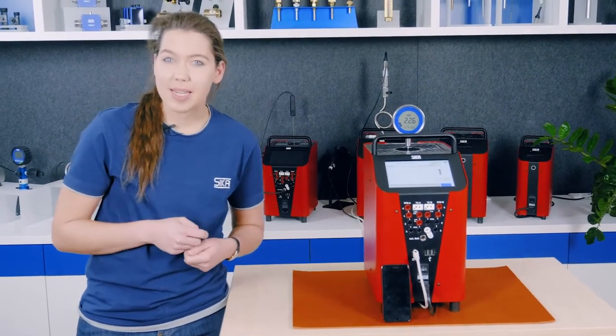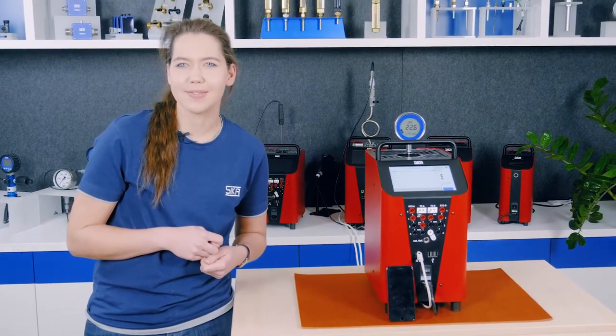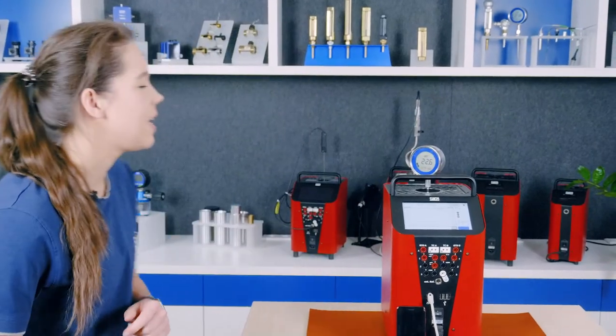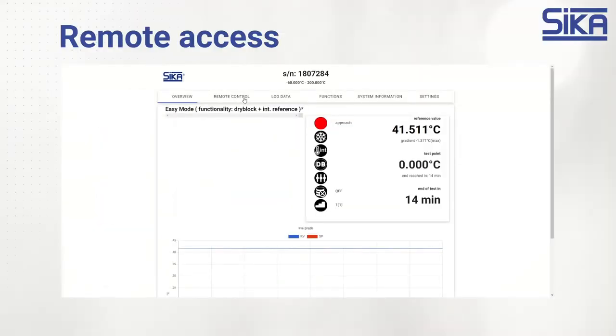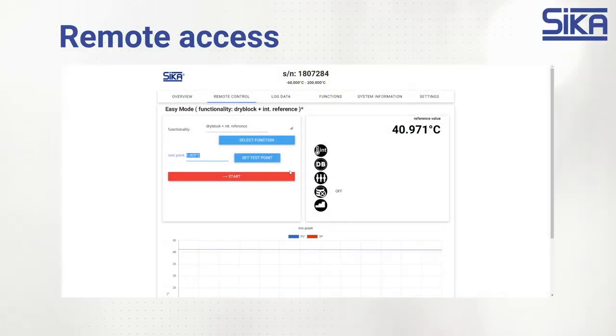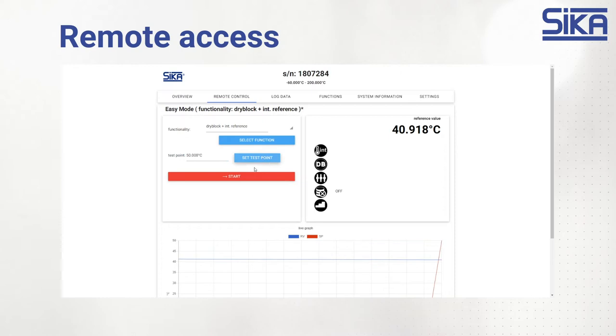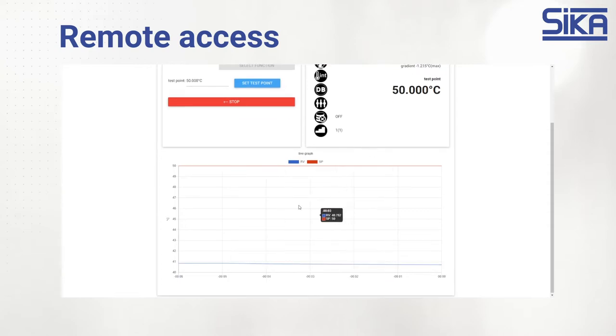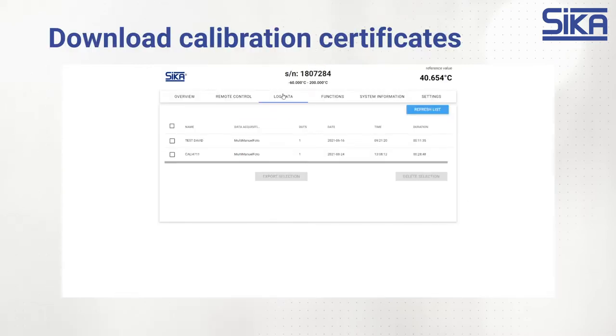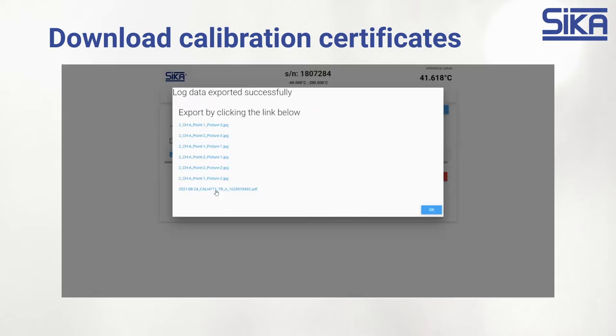The web app can offer you several important and workload-reducing functions. You can start a calibration process remotely, for example. Simply enter the desired temperature in the field and press start. The measuring point is now approached and shown live in the chart below. An additional key feature is the ability to conveniently download all the calibration certificates from the network.